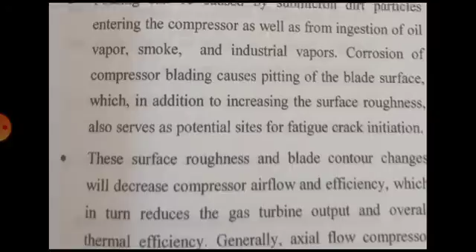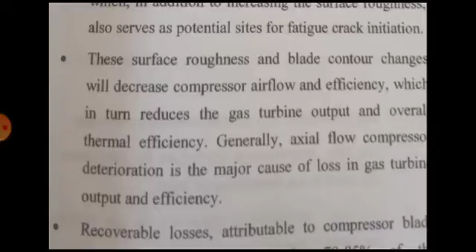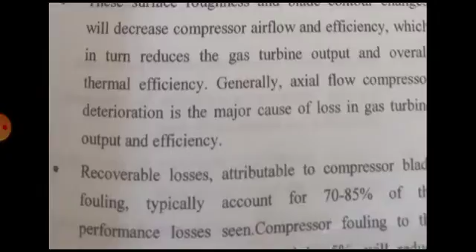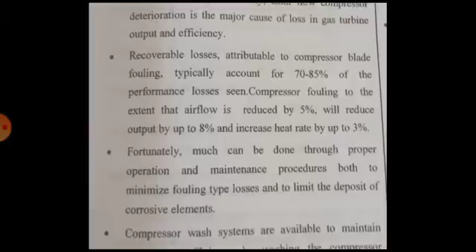Okay, this surface roughness and blade contour changes will decrease compressor airflow efficiency, which in turn reduces the gas turbine output and overall thermal efficiency. Generally, axial flow compressor deterioration is the major cause of loss in gas turbine output and efficiency. Recoverable losses attributed to compressor blade fouling typically account for 70 to 85% of the performance losses seen.